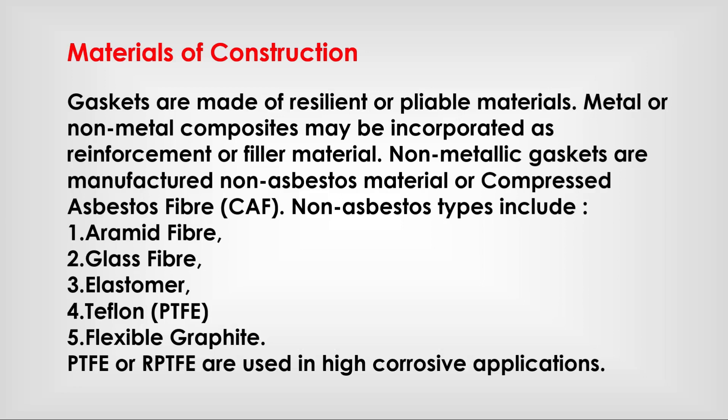Non-metallic gaskets are manufactured from non-asbestos material or compressed asbestos fiber. Non-asbestos types include aramid fiber, glass fiber, elastomer, Teflon, and flexible graphite. PTFE or RPTFE are used in highly corrosive applications.